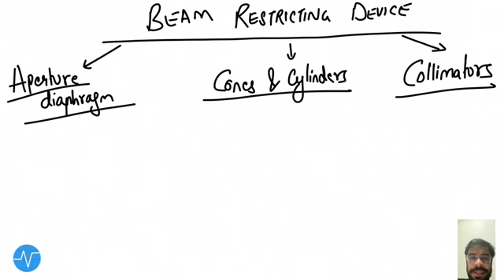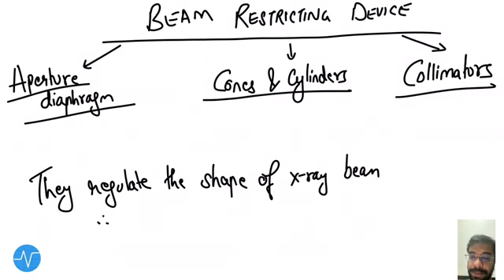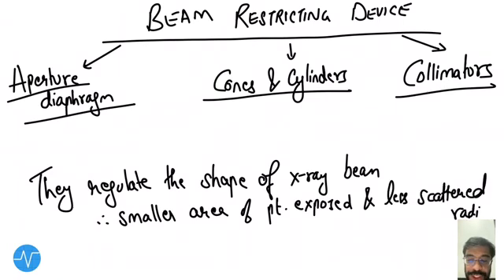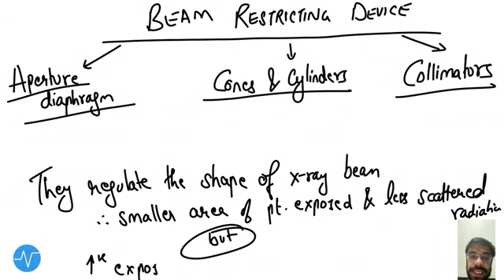Beam restricting devices — there are three types: aperture diaphragm, cones and cylinders, and collimators. What they do is regulate the shape of the x-ray beam, so a smaller area of the patient is exposed and there is less scattered radiation. The disadvantage is that there will be increased exposure to the patient to compensate for image quality.